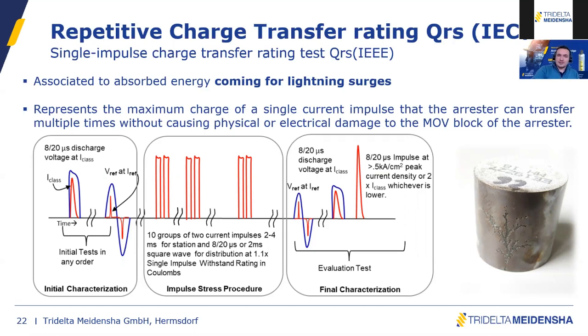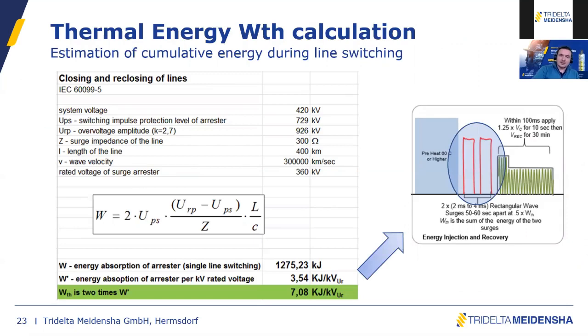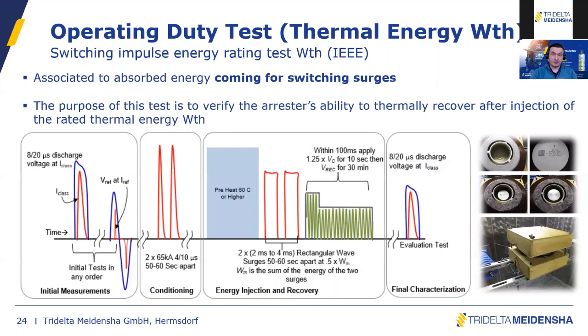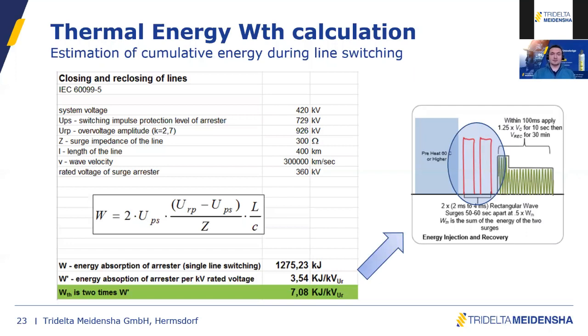Yes, and this is the difference with the next energy test, which is called thermal energy from the operating duty test, which is more a test to verify the thermal recovery. This is more related to a switching, to a breaker reclosing operation. Actually in the IEEE standard, it's called the switching impulse energy rating test, but in the IEC, it's called the thermal energy test. So as I said, it is mainly associated with switching.